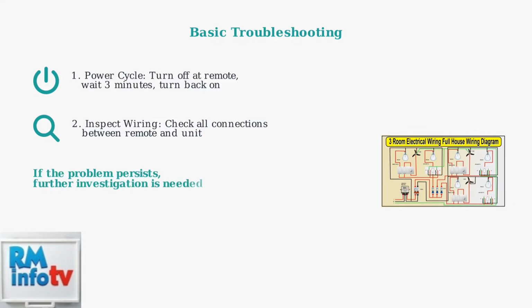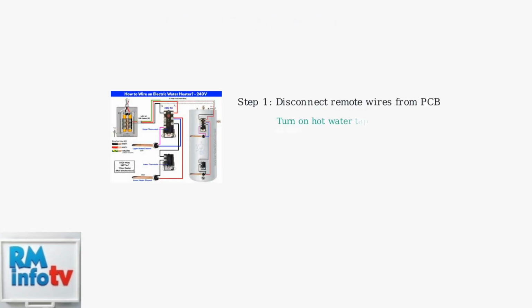If the problem persists after these basic steps, further investigation is needed to isolate the specific cause of the communication failure. When basic troubleshooting doesn't resolve error code 76, we need to perform more advanced diagnostic steps to isolate the problem. First, disconnect the remote control wires from the PCB and turn on a hot water tap.